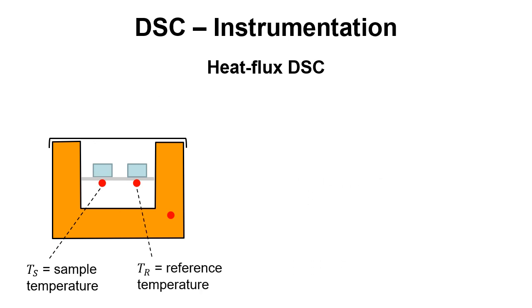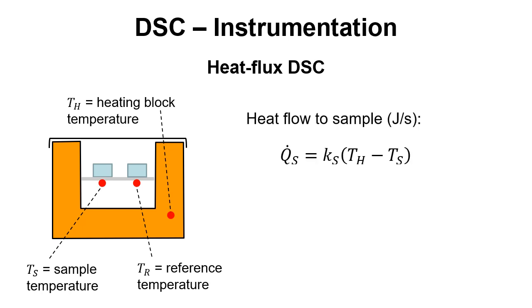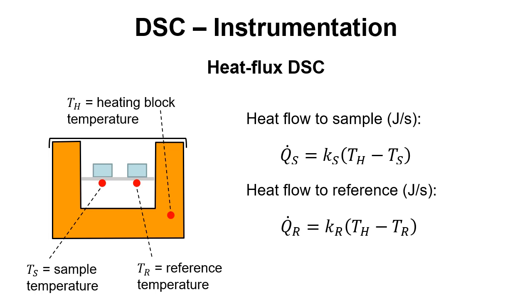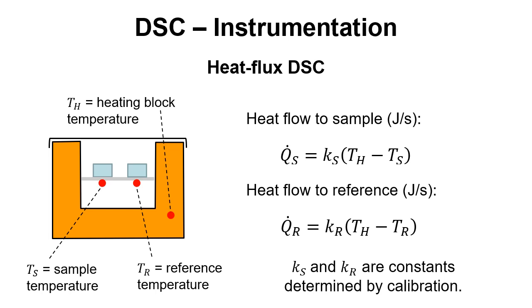We have T_S the sample temperature, T_R the reference temperature, and T_H the heating block temperature. The heat flow to the sample is given by the equation: Q-dot_S equals K_S times (T_H minus T_S), where K_S is a constant and the dot indicates a per-second basis. Similarly, the heat flow to the reference equals K_R times (T_H minus T_R). K_S and K_R are constants determined by calibration. This allows us to record and monitor the heat flow to the sample and reference, and it is the difference between these that we are interested in.